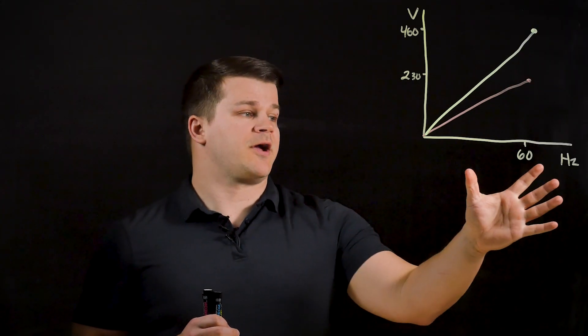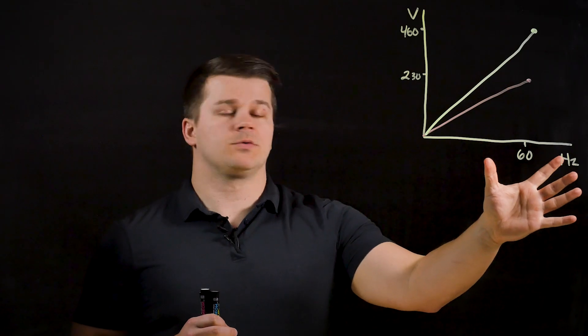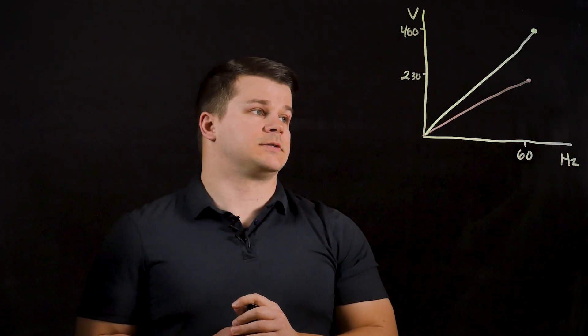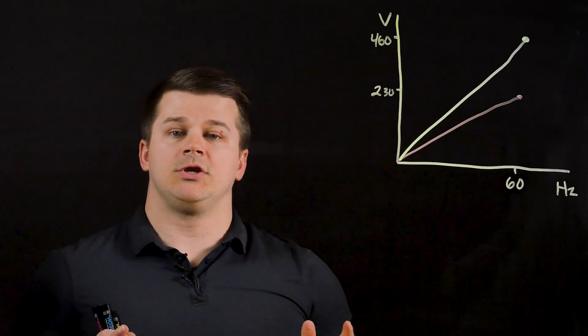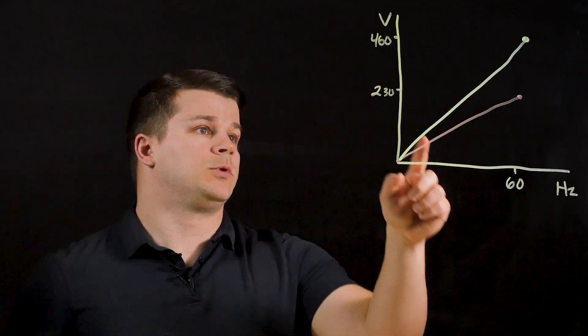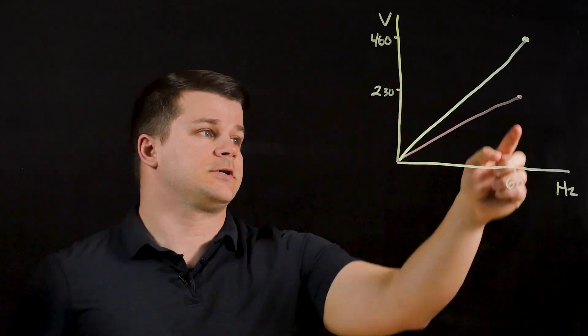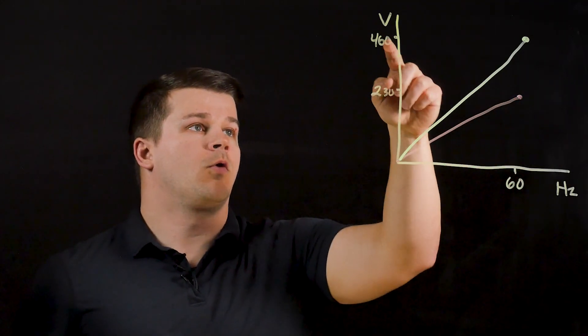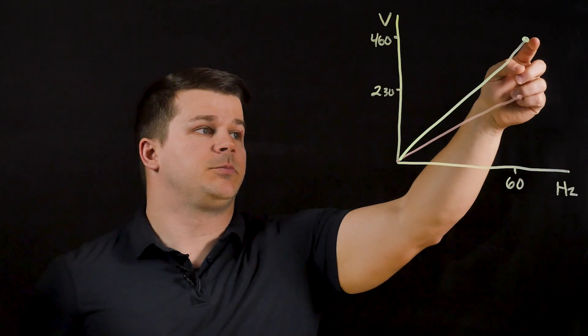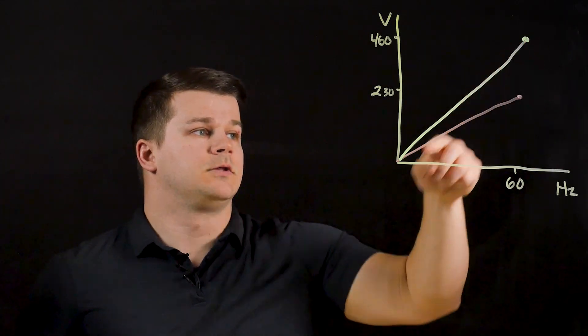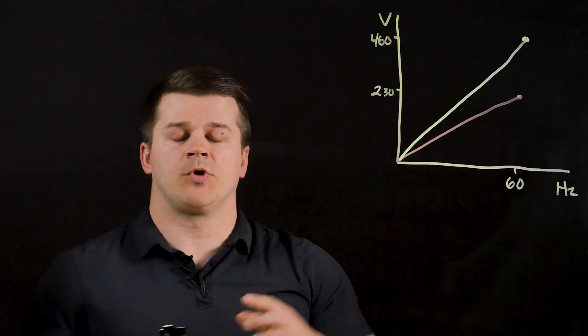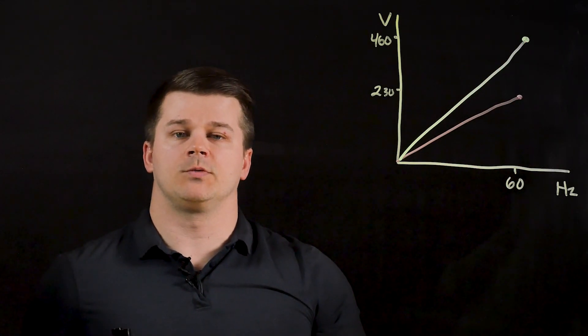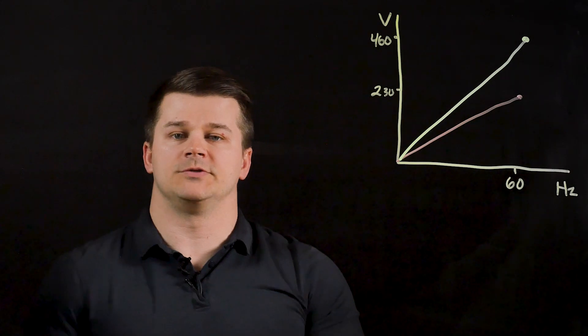In this graph you can see the frequency on the x-axis and the voltage on the y-axis. A common US winding will be 230V 60 Hertz as seen here, or 460V 60 Hertz seen up here. These lines represent the two different ratios between frequency and voltage of these motors.